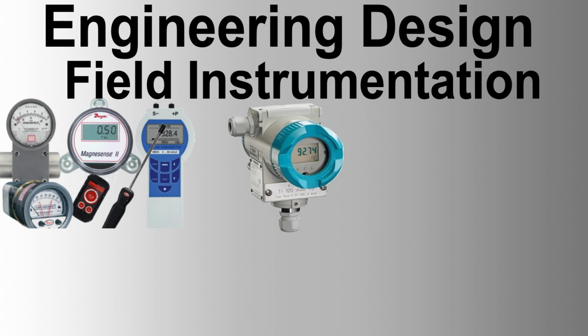Temperature transmitters must have a duplex 3-wire PT100 RTD for the temperature range of -200 degrees Celsius up to +400 degrees Celsius with SS316 sheath and mineral insulation. In general, transmitters must have integral temperature elements. Remote transmitters must be considered in specific cases, such as applications with high vibration, poor access, or in exposed locations where the transmitter needs protection from the sun by a sunshade.